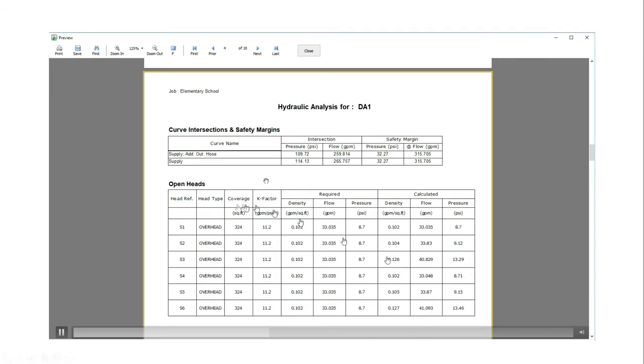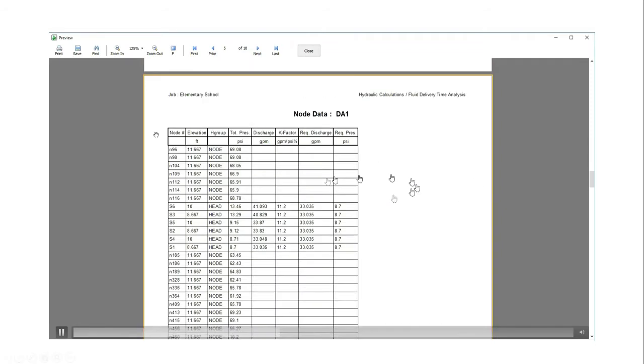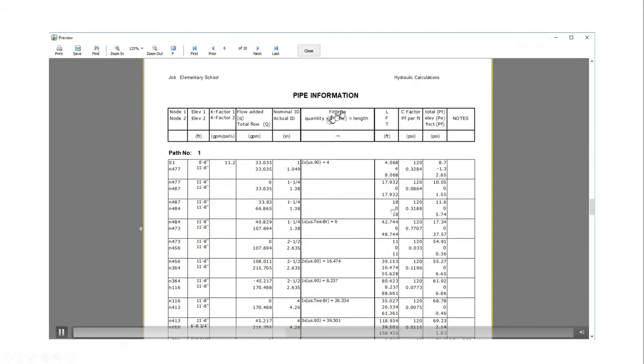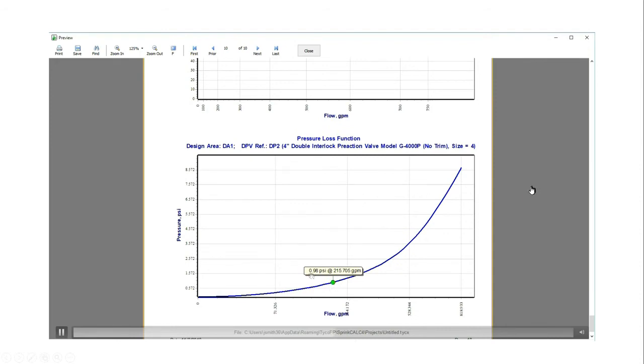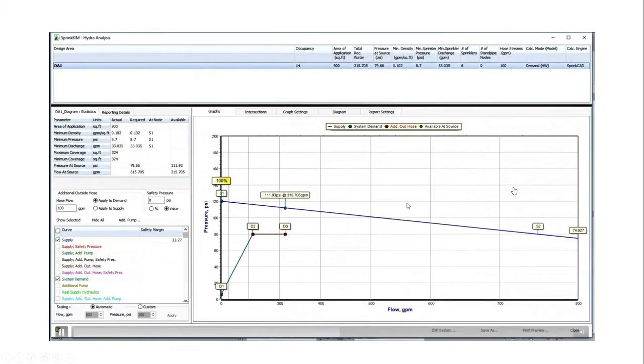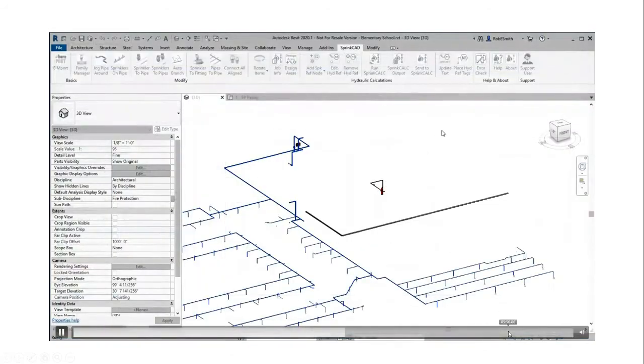Now showing the results as a printable file — it could be saved as a PDF or sent to a printer. It's the same basic information presented as a report: hydraulic analysis including water supply, hose data, sprinkler flows, required pressure and flow at the source. There's the water curve and the curve intersection showing safety margins. Then there's an open heads table, which I find very helpful — you can see what you set for coverage and K-factor, the required density, flow, and pressure, and then on the other side the actual values. This is the node header defined by NFPA 13, and the pipe header defined by NFPA 13. Every piece of pipe in your calculation is represented in the pathing report, with the most important information in path number one. The report is customizable.